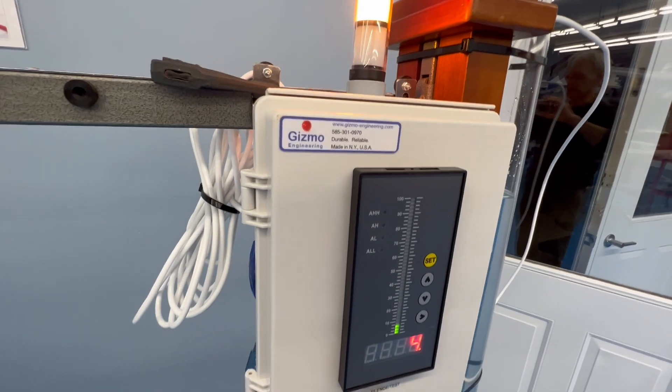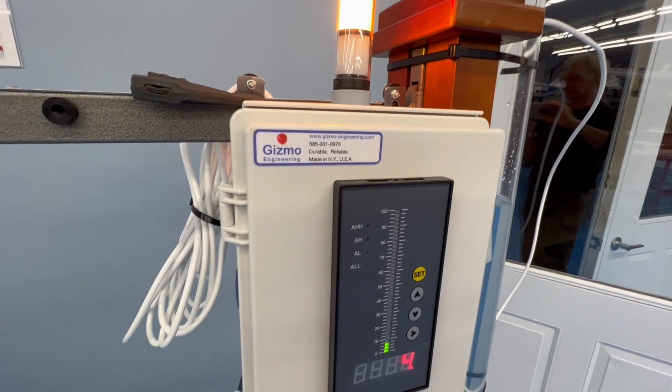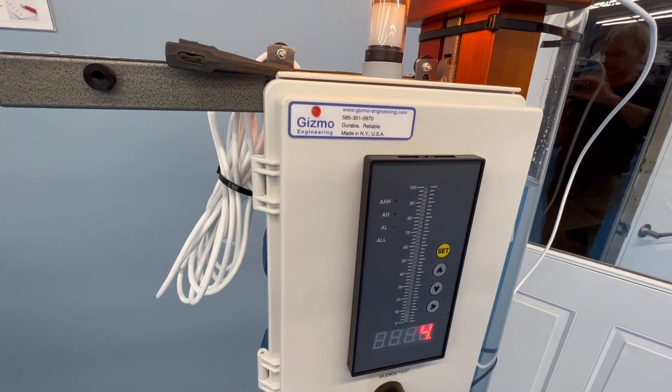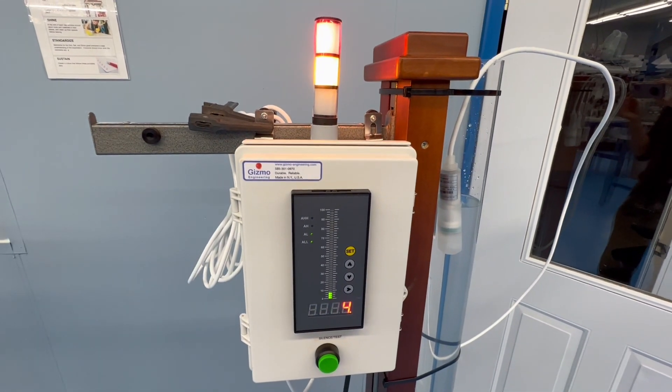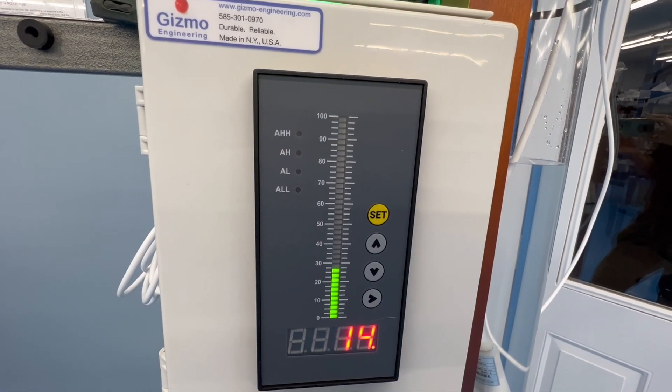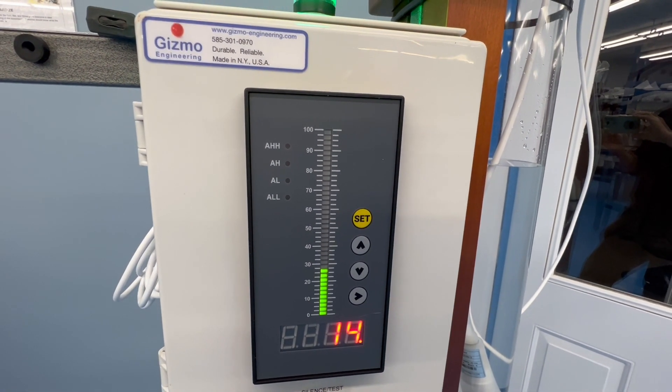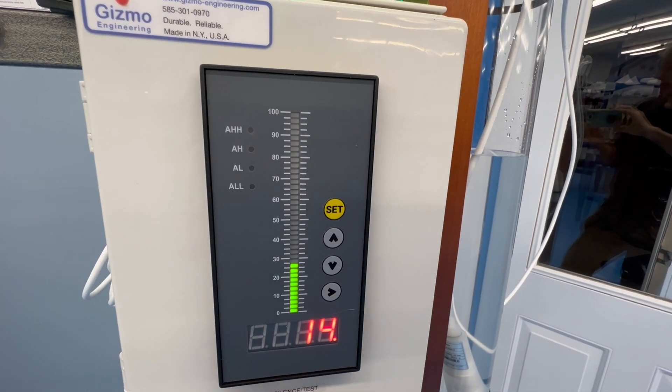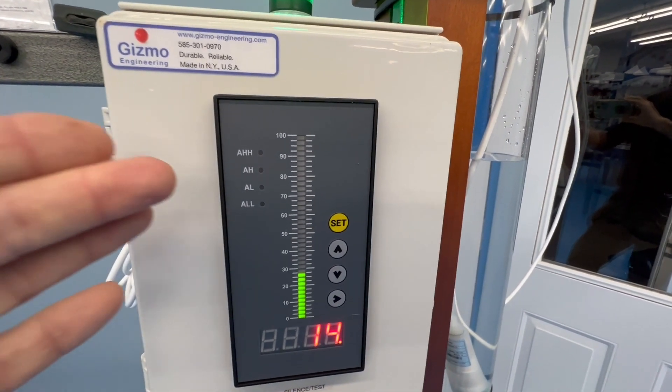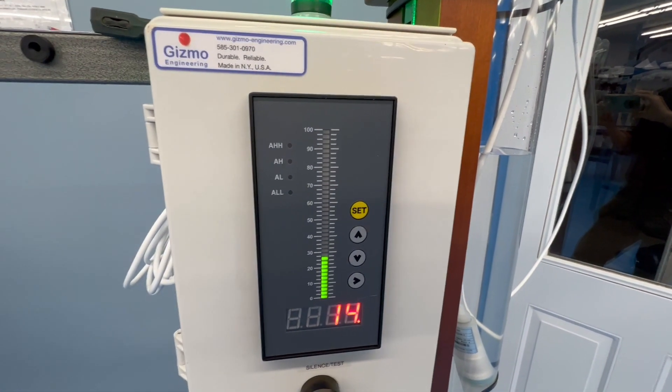So that silence button can be set so that it comes back after 30 minutes or it just rings one time until the level's corrected. The relays can be set up so they can send an email using our email module or a text message or connected to a building alarm system, whatever behavior you want the relays to have, it's possible to do that.